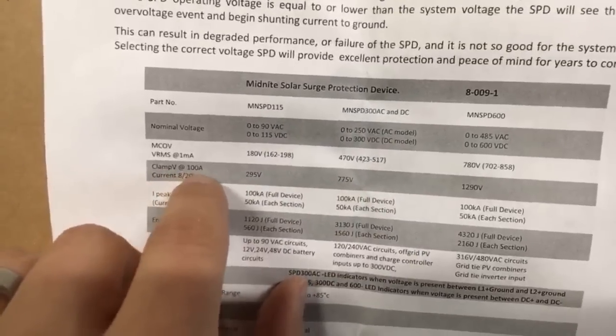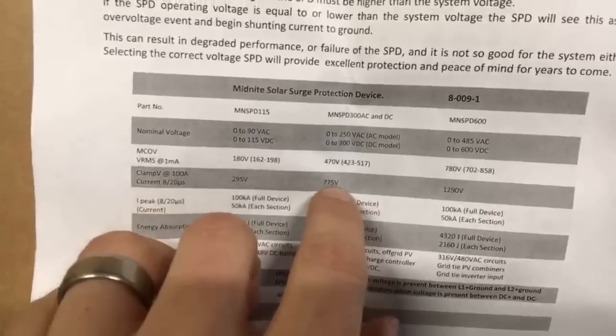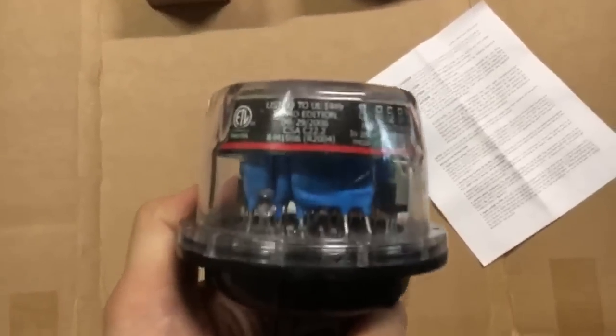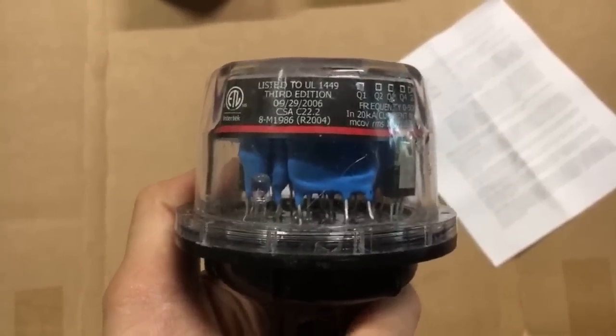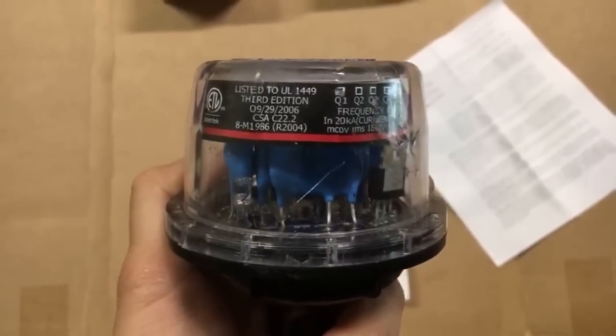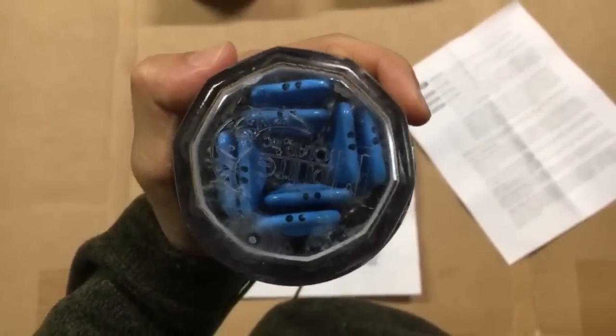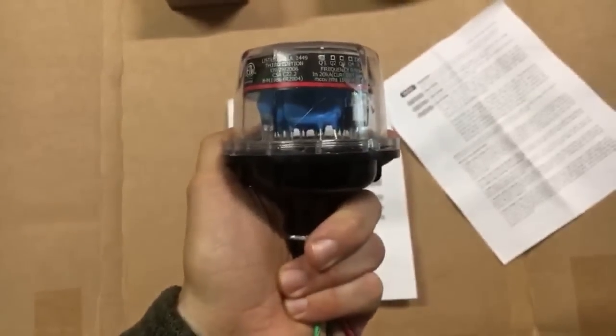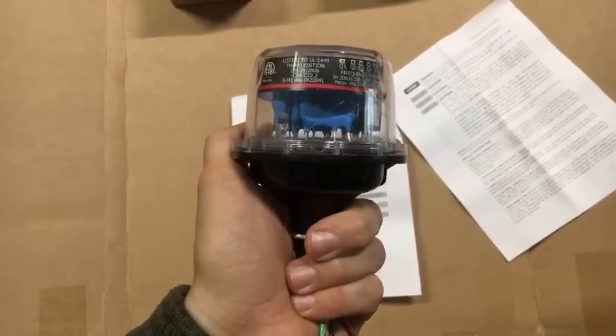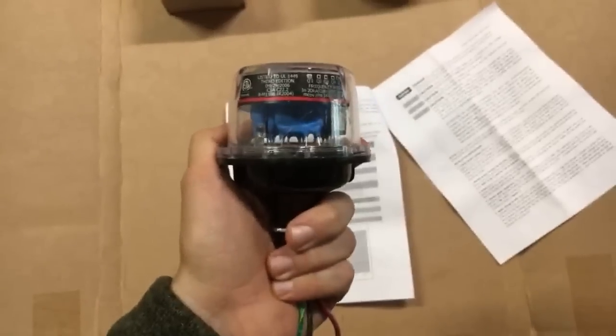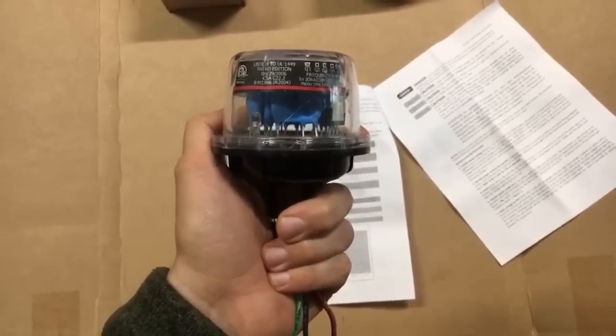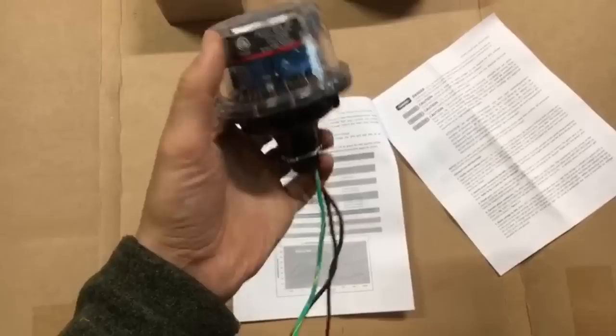The clamp voltage at 100 amps starts clamping at 775 volts. Again, not an electrical engineer, but basically what you have is a device that, when it sees voltages that could be coming from some kind of surge - usually over the grid connection from lightning, but it could also be lightning hitting a tree near a solar array - this is going to grab that voltage and hopefully shunt it to ground before it tears your stuff up.